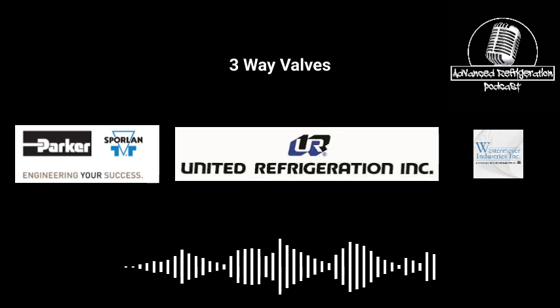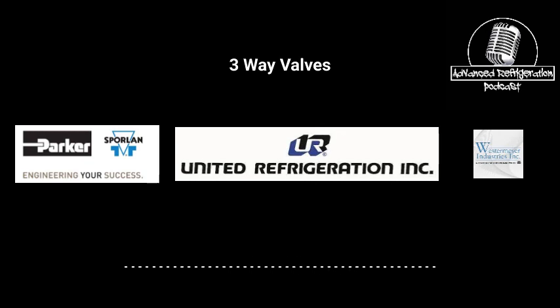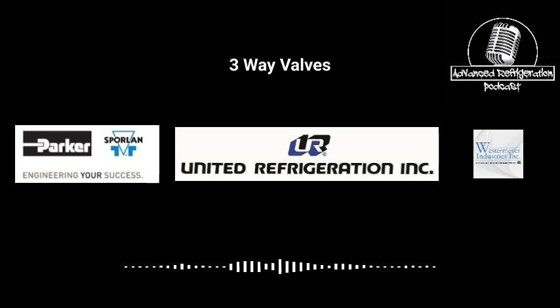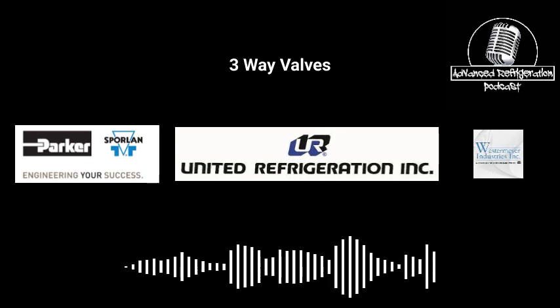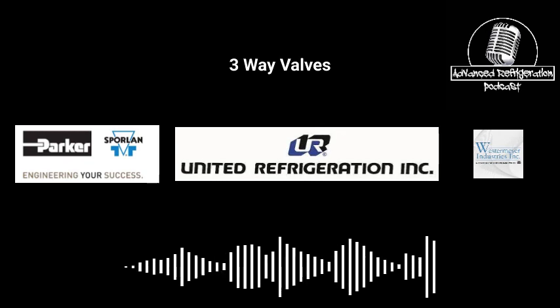So the way this whole thing works is it works like a hydraulic cylinder almost. When you apply pressure one way, it closes the plunger and pushes the piston down. When you vent that pressure out of the cylinder, it's going to allow it to go to the suction header or suction, and it's going to allow that gas that built up in that chamber to relieve itself into the suction header, and it's going to allow that piston to come up, and it's going to shift it the other way.